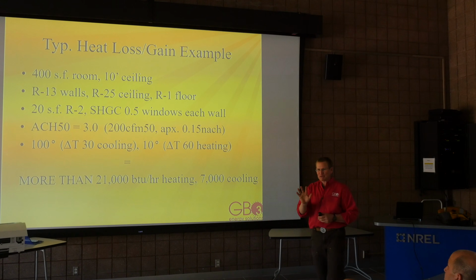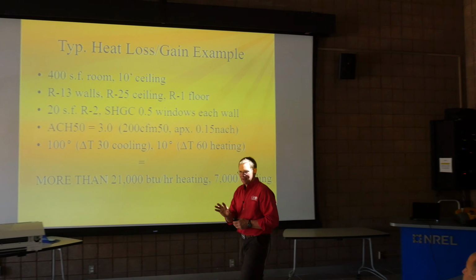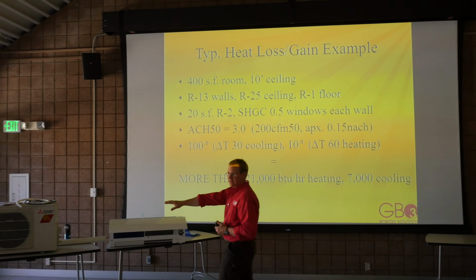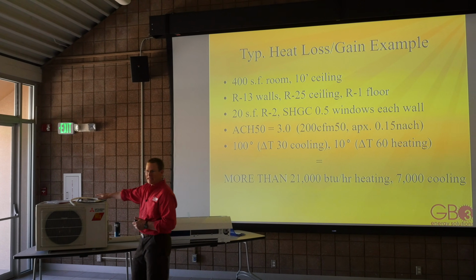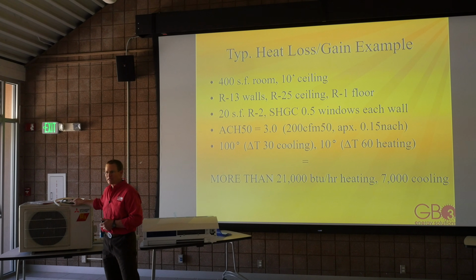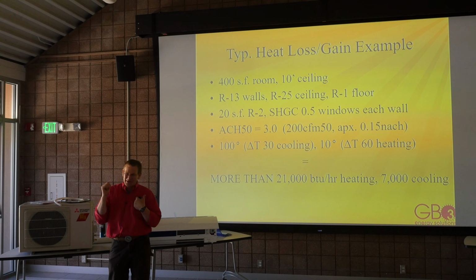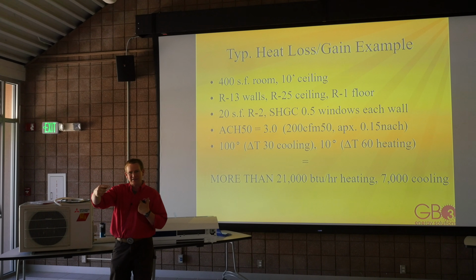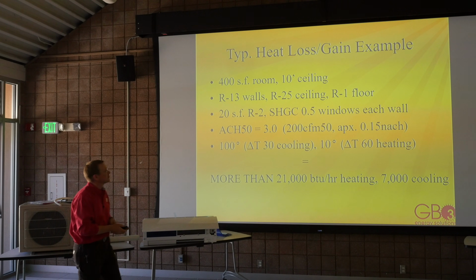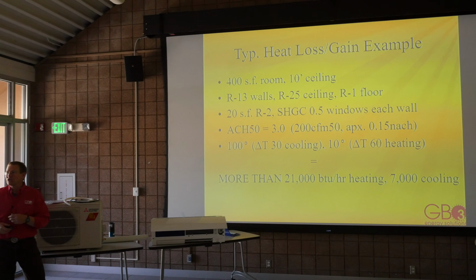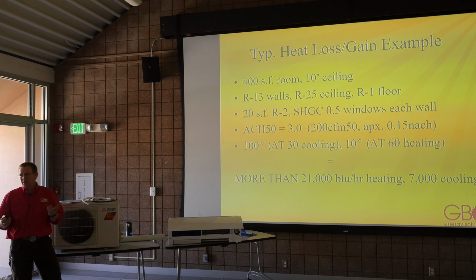Heating loads are always bigger than cooling loads, right? So anytime I install one of these, I size it for heating. If I size it for cooling, come winter, they're going to be sad. They're going to be cold, and I'm going to be sad because they're going to call me and I'm going to have to replace it because I made a mistake. You always have enough cooling capacity if you size it for heating, because the heating and cooling capacities on these are very similar.